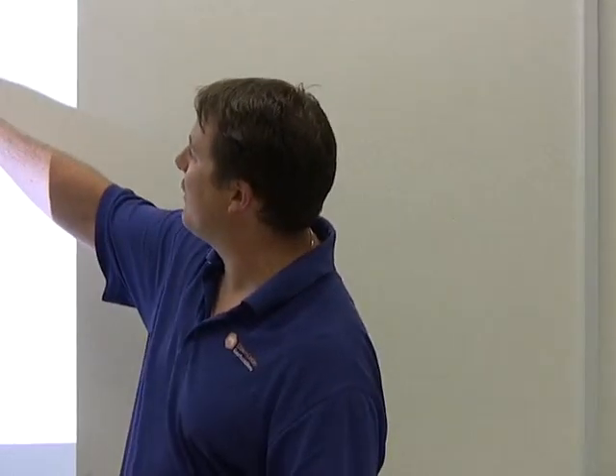So yes, we're now very, very careful about what cables we get. At the back of these nodes, it gets very hot, and really simple things can cause all sorts of problems. We had one power cable that actually got fused inside the socket. So we had to power it off and then get in there with a pocket knife and cut right around the socket to get the power cable out before we could replace it. So you can have all sorts of interesting problems. Yeah, it's the sorts of fun you have when you just have thousands of things plugged in.